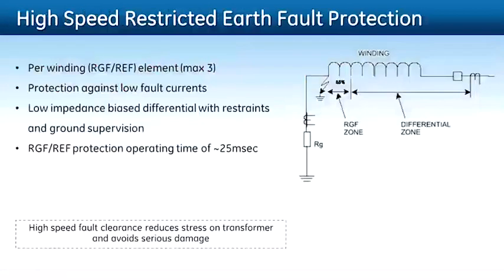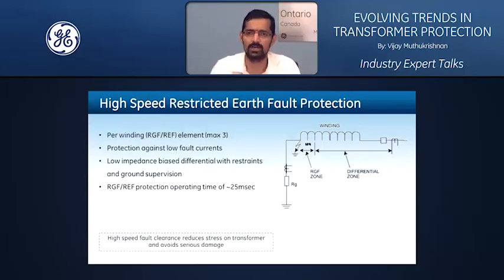Now, the differential functionality can give you coverage for a certain percentage of the winding. Obviously, if the fault is in the portion of the winding closer to the neutral end of the transformer, you will definitely have challenges detecting it using differential functionality. That's where you need restricted earth fault, which is meant for low levels of fault current towards the neutral. So any transformer protection relay you are looking at should support enough restricted ground fault protection. For example, whether you have a 3-winding or 2-winding application, you should be able to apply restricted ground fault up to 3 windings depending on the nature of your winding configurations.